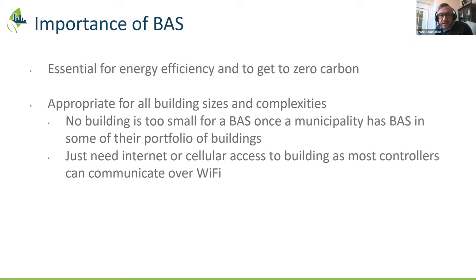The BAS manufacturers, many of them are producing modular type components, and they also have a lot of smaller controllers to handle smaller facilities with fewer points. All they really need is internet or cellular access to Wi-Fi. For example, even small places with maybe a unit ventilator or shed, we're seeing more and more a controller that will monitor key points and deal with optimizing that space.